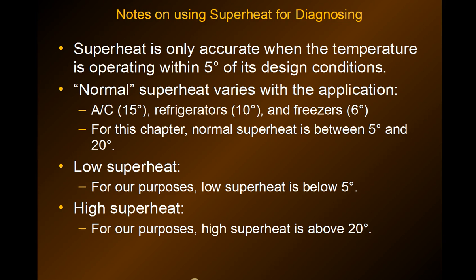If you have a cooler that is brand new and you're doing a startup, the interior is at ambient air temperature — it could be 80 degrees inside when the design conditions are between 35 and 40 degrees. So if you're not within 5 degrees Fahrenheit of the design conditions, superheat goes right out the window.